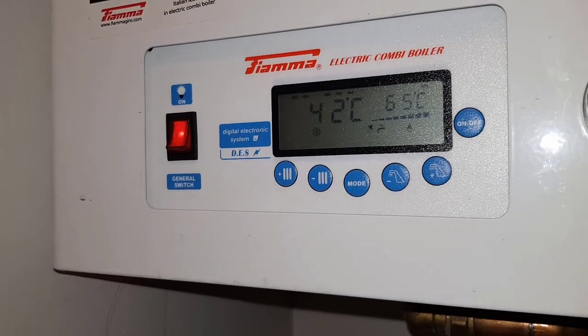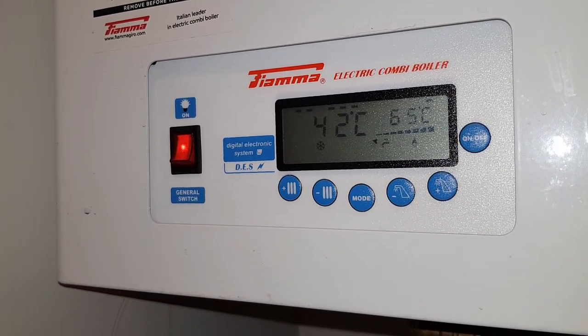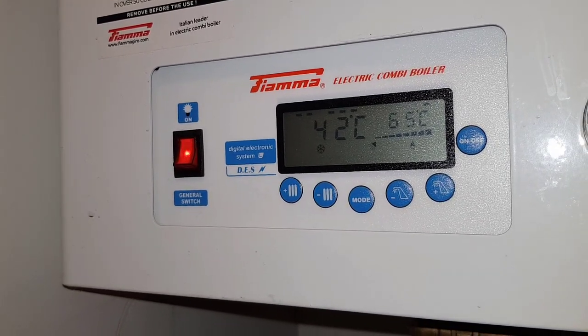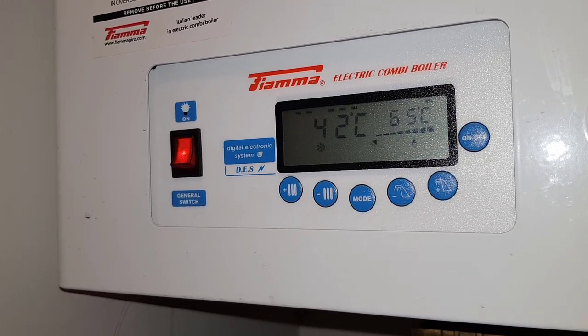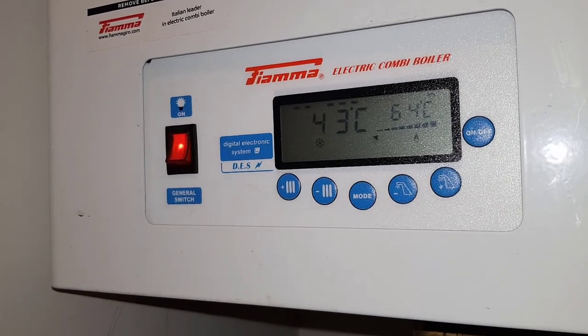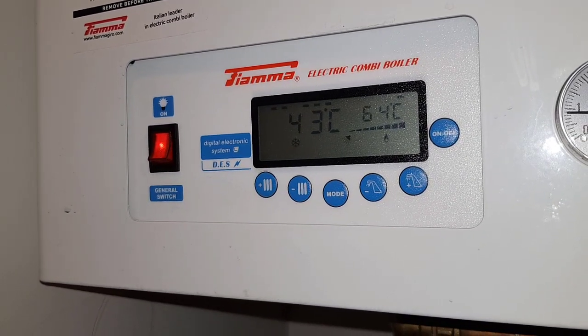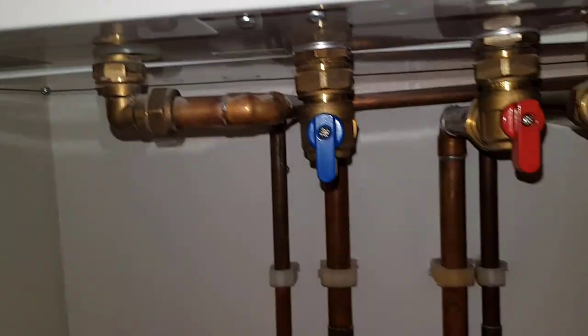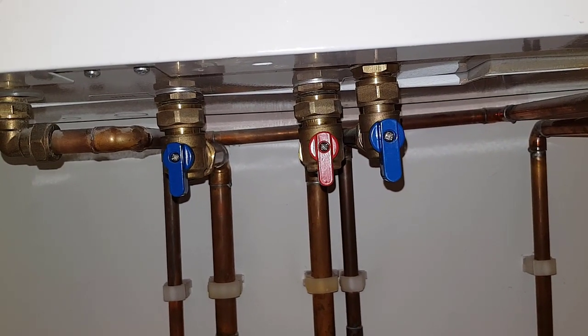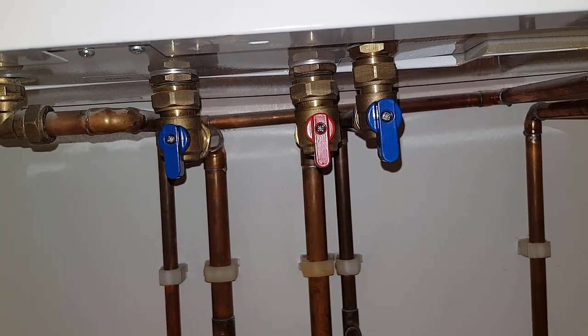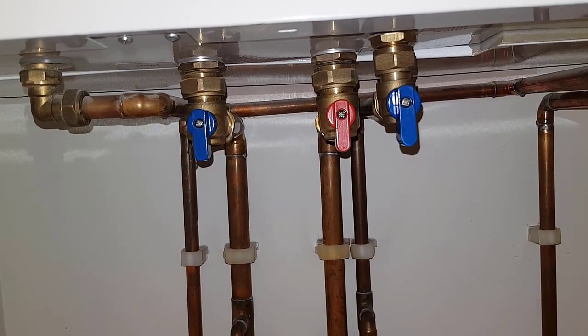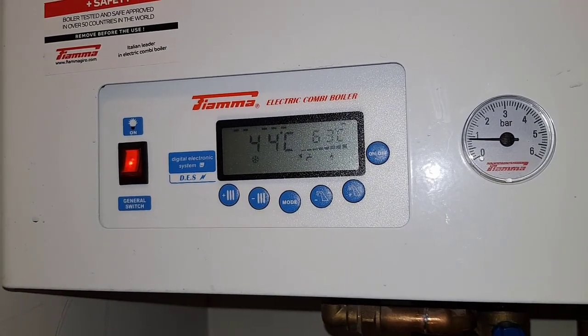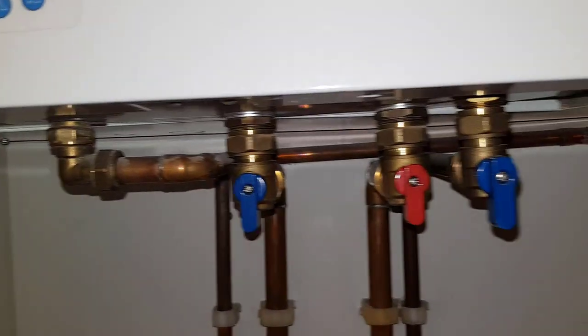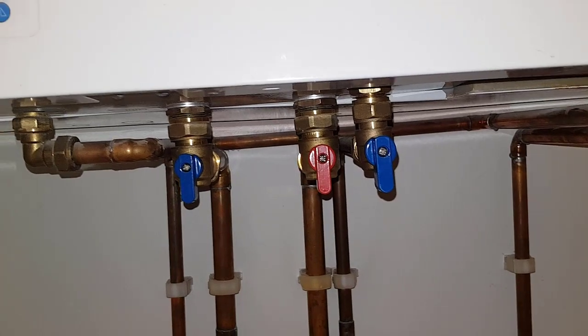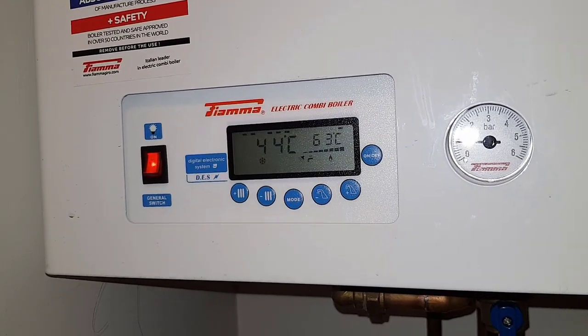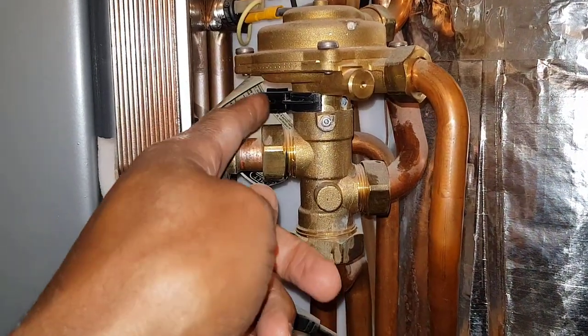Now let's turn the tap off, because now the tap's turned off, the pump should have stopped also because it's not required, but it's still running. And then what happens next, the flow pipe for the heating will start getting hot, and the radiators will start getting hot. So that's the problem. It's not turning on when it should for the hot water, and it's then not turning off because it's heating the radiators. That's the fault, and we're going to try and figure out what's going on.